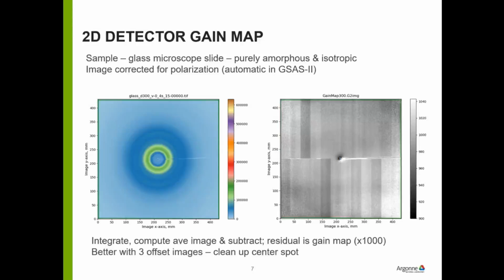And there is an additional technique that uses 3 images which are displaced sideways, about 5 centimeters that way and 5 centimeters that way, and one in the middle. And for that, you can use that to clean this up. Notice that as you go across this detector, first of all, there's a funky little gap in here between the set of panels that are above and below. I have actually seen some of these things where the individual panel is slightly skewed a little bit.